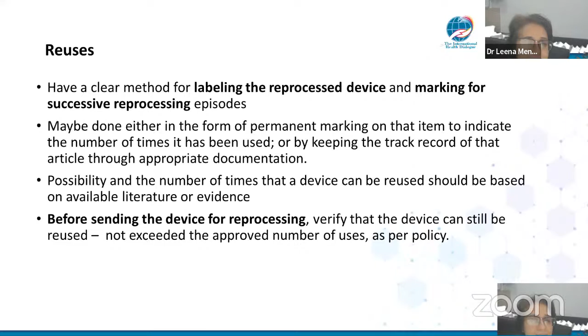So once the process has been done, we need to also have the discarding very clear as to when to discard it. Firstly and foremost, as per the number of reuses. If your device is still fine and it can be reused further, but if it has met the number of reuses, you cannot be reusing it further. So discard and document that it has been discarded due to it meeting the number of reuses. Again, one needs to have a specific rejection criteria, very specific to that device. For example, if it is a lumen or something, and maybe sometimes after 2 or 3 uses, the blood clot sometimes gets just stuck there. It just does not get dislodged. And once that is there, one should not be using it, even if you have not met the maximum number of reuses you have specified. So that can be one of your rejection criteria.